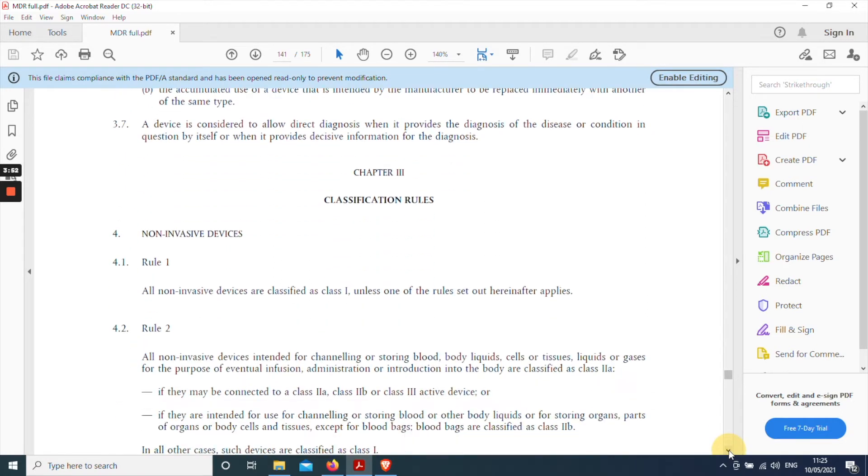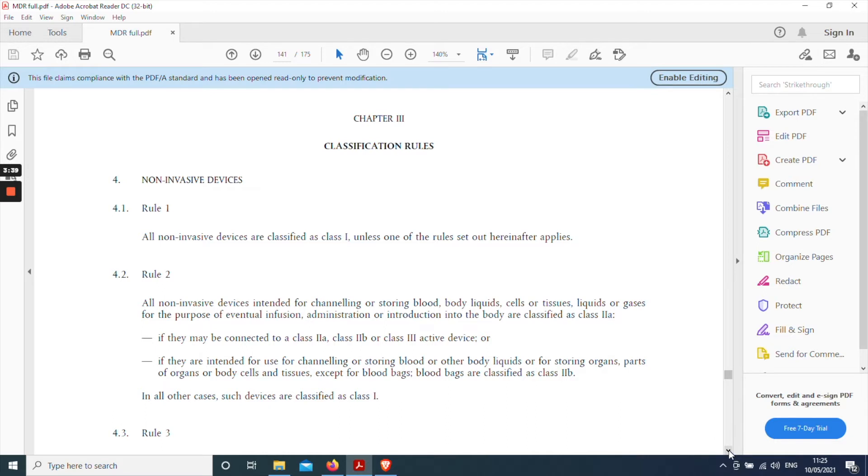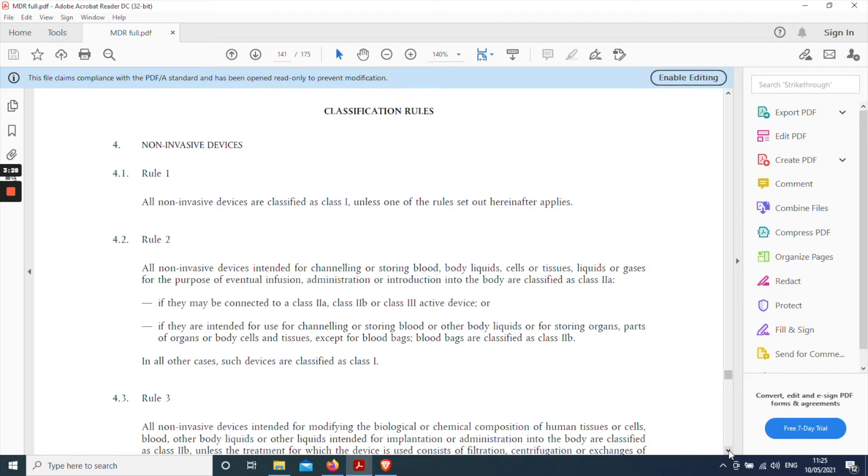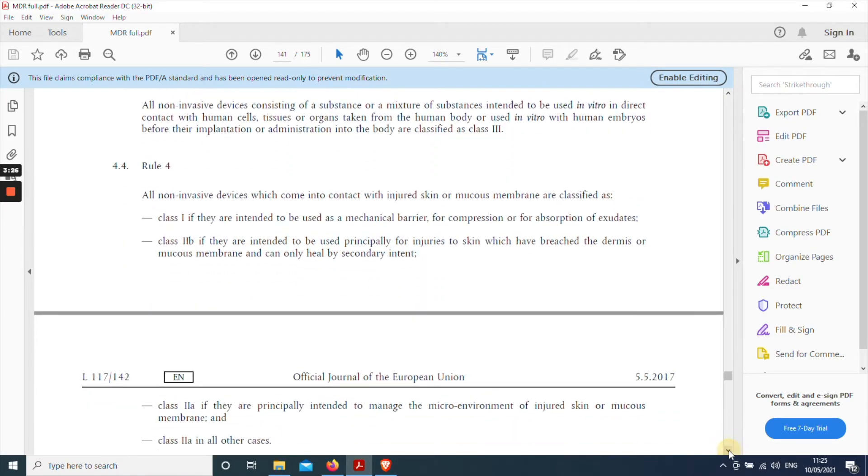So if you look at the first part of chapter three you can see it contains part four non-invasive devices. So all of the rules underneath part four relate to non-invasive devices which is not relevant to a cardiac pacemaker which of course is a surgically invasive device. So we can skip straight over all of the rules under heading four. So that's rule one, two, three and four.